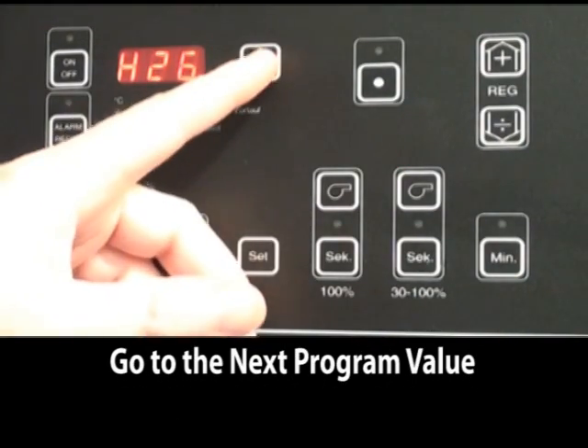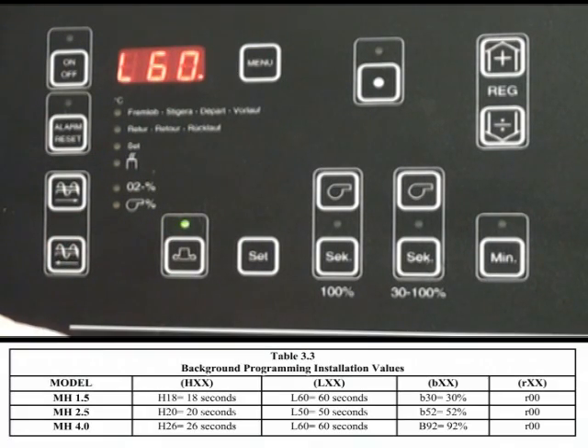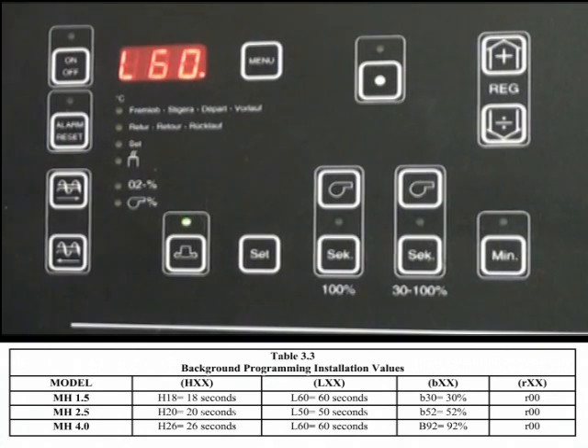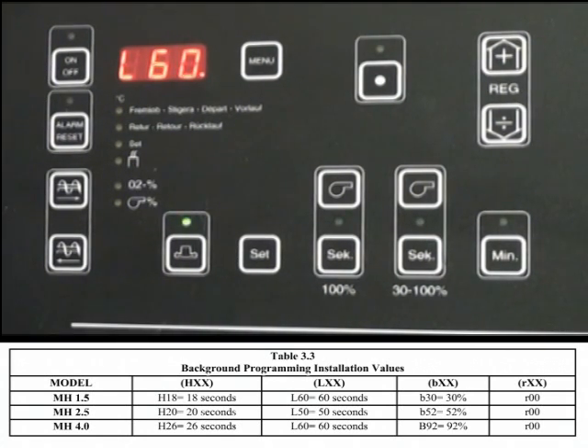Continue through the menu. The next setting is for maximum time allowed in seconds between auger pulses. This should be either 50 or 60 seconds depending upon the model of the boiler.